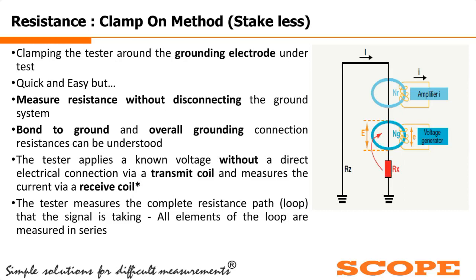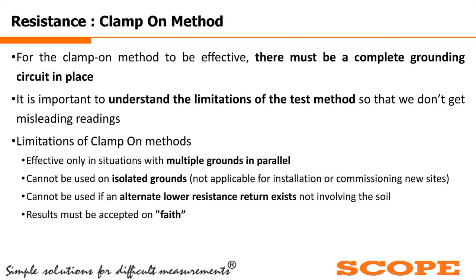Generally this clamp-on type of method requires a complete resistance path. A complete resistance path means all the elements present in the loop are measured in series, and due to that this method is only effective whenever a complete grounding circuit is present. We cannot use this clamp-on method on a grounding system where it is not connected, or on an incomplete grounding path. So the major limitation of the clamp-on method is that it will be effective only in situations with multiple grounds in parallel. Also, this type of clamp-on method cannot be used for isolated grounds, as I said earlier.